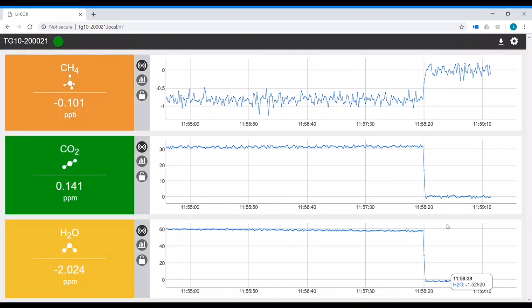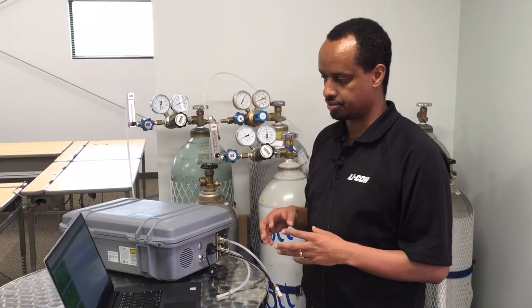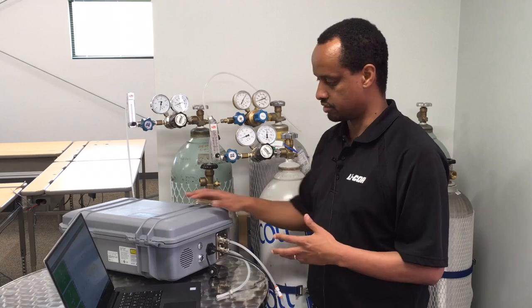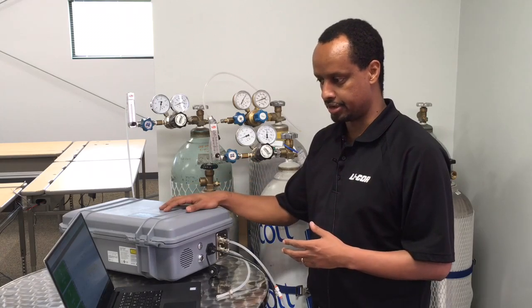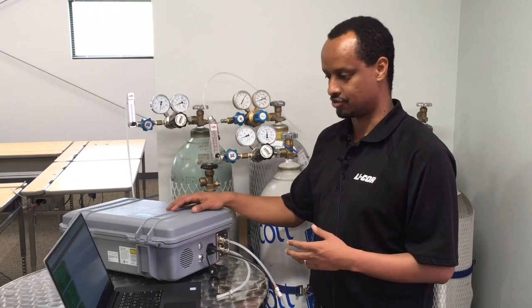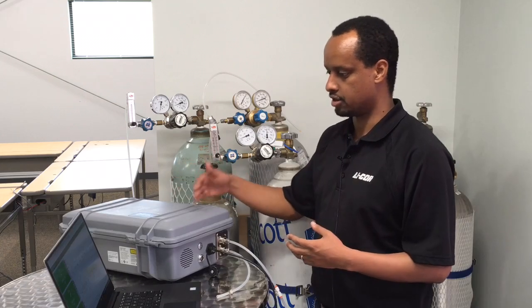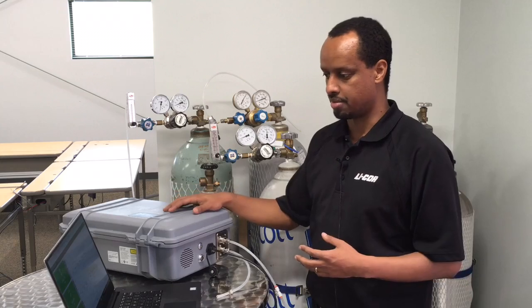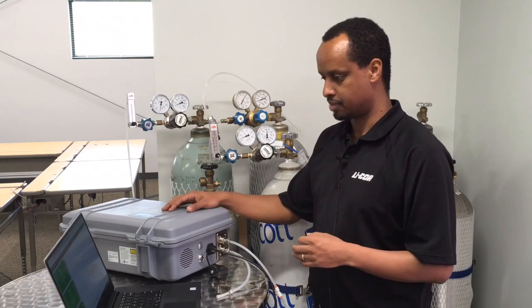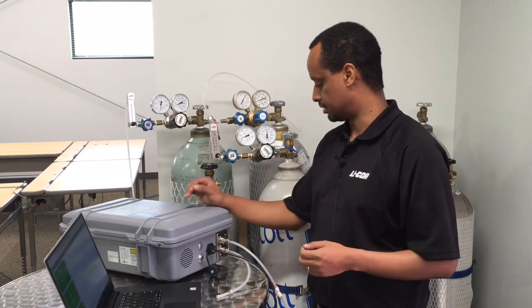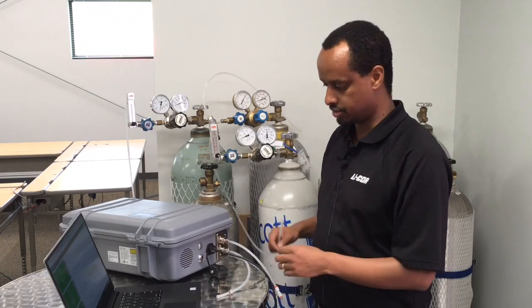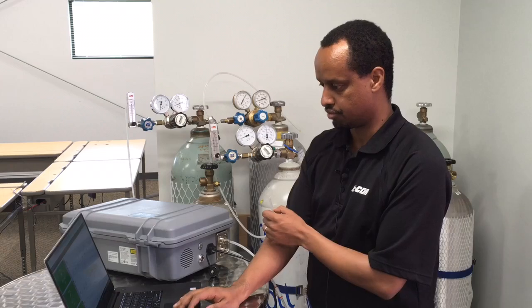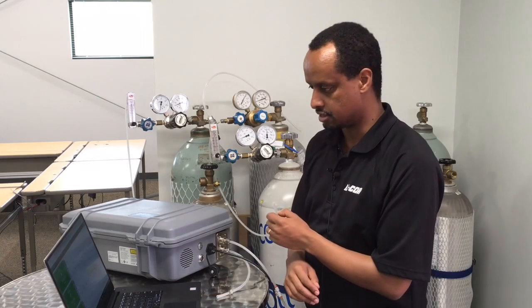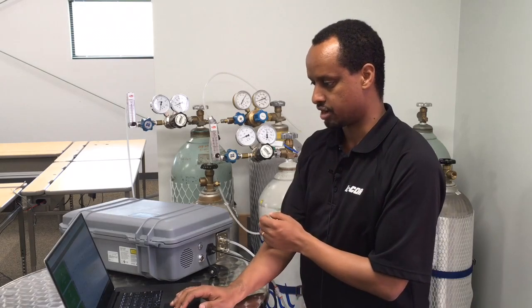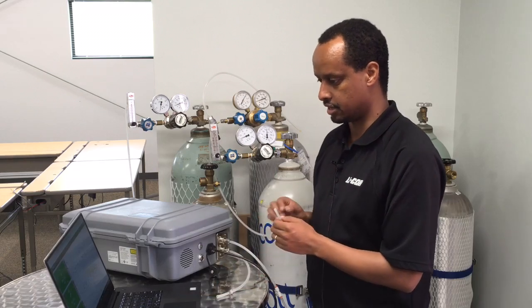And when we do span, it will primarily be for methane, and we'll go ahead and do the span now. Okay, so we're ready to perform the span for the 7810. So this is a 7810, a primary CH4 instrument. So all the spectroscopy is optimized for methane, and the water and CO2 follow what we do for methane. So when we do the calibration, we primarily calibrate the methane, and the same span adjustment that gets applied for methane will be applied for CO2 and water as well.